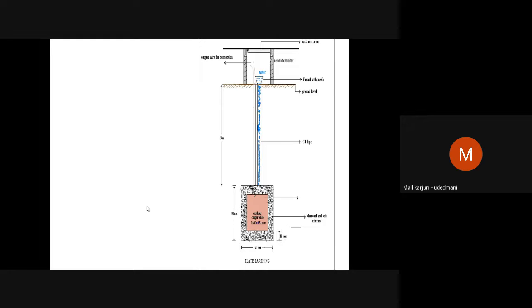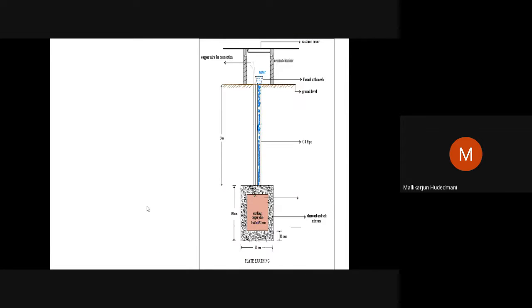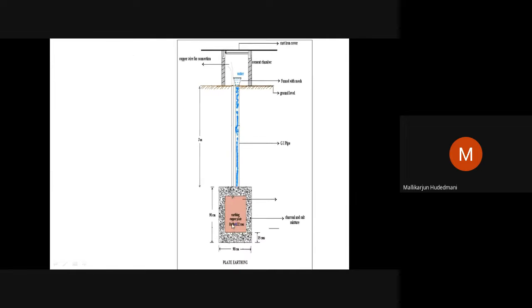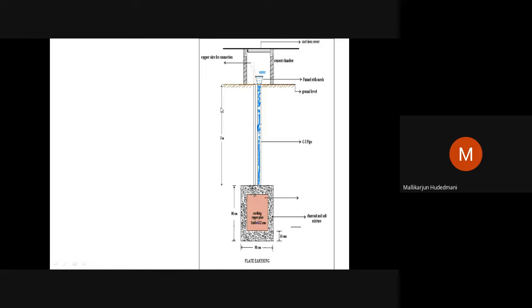Suppose I think of the same mechanism for industry. In industry, we will have a very high fault current. The same mechanism is done in this way, the plate mechanism. Can you see this plate mechanism? And just go down this way. This has a GI pipe from the earth surface here, you dig down and assemble the chamber mounting, and a GI tube 3 meters deep down.